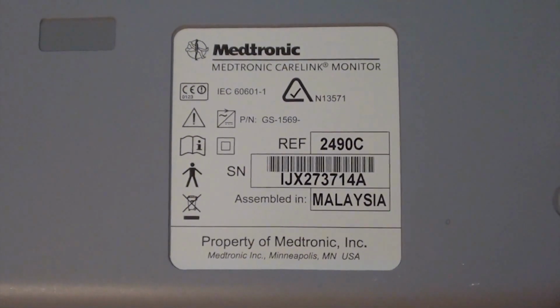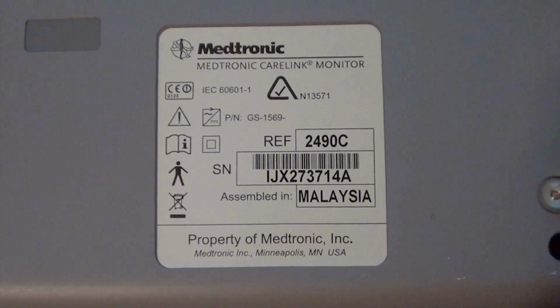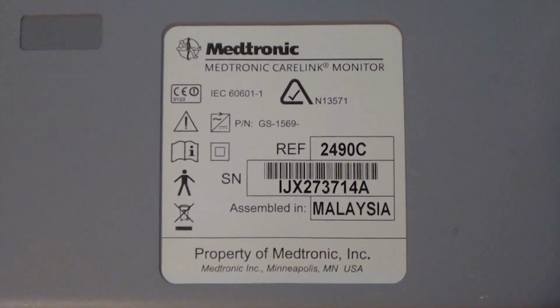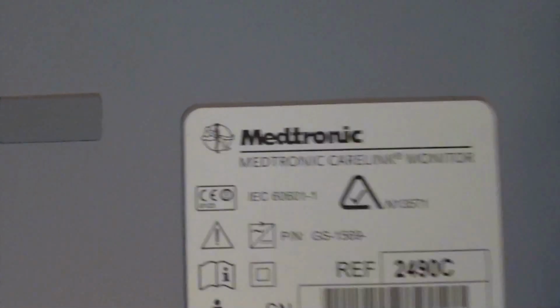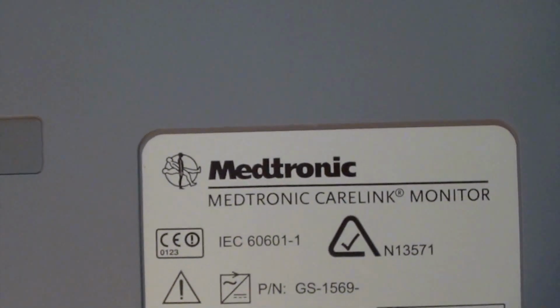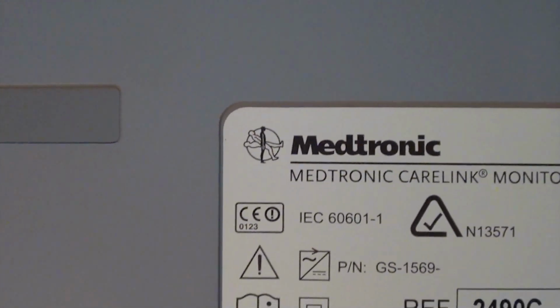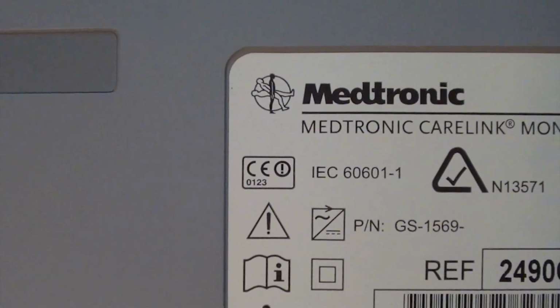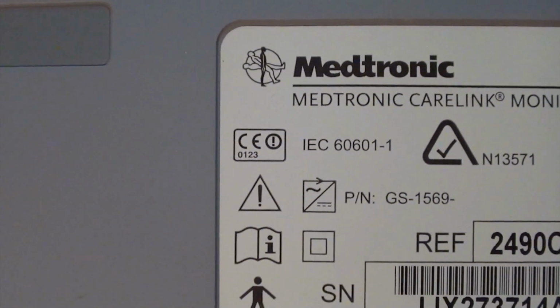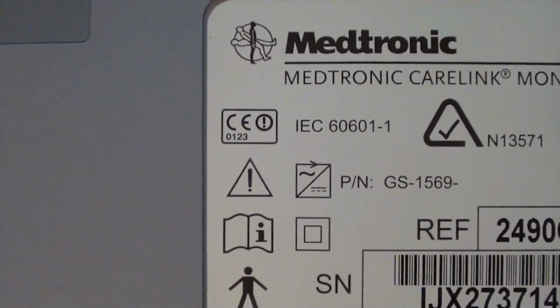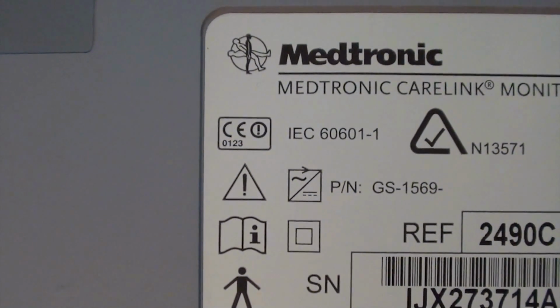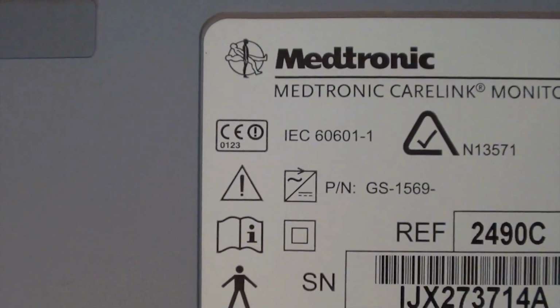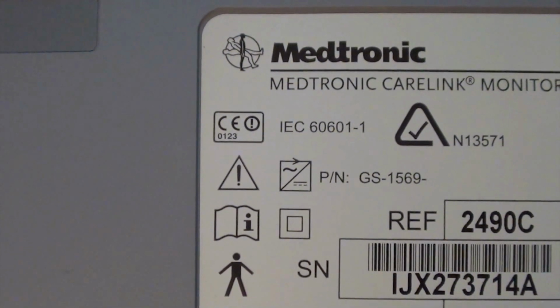Well, on the underside of the unit we have a small label, and on this label is quite a lot of symbols and logos, so I'll go through some of these with you now. At the top here we've obviously got the Medtronic logo, but below that we've got this CE logo. Now what's interesting about this is it's in a box and it has a number below it, which is 0123. What this means is that the device has been classified for use as a medical device.